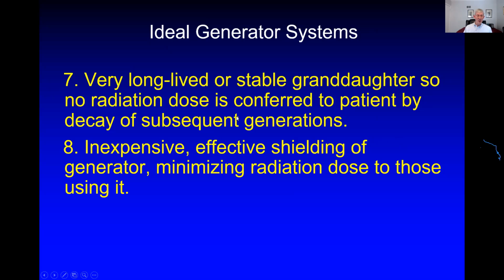Lead is a very soft metal. It can be molded to any shape imaginable. In fact, 48 pounds of lead are in that 48.2 pound generator. The other couple of ounces is simply the fluid path, and you're going to see a photo of that pretty shortly. That will minimize the radiation dose to the people who are handling the generator, who are shipping it, who are carrying it down our hallways and so on.